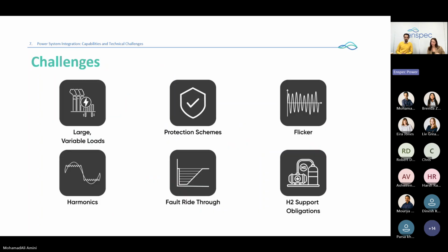In addition to these capabilities, there are some challenges that may arise at the point of connection of a hydrogen electrolyzer plant, mainly because they are large-scale variable loads, as seen in previous slides. These large-scale variable loads could cause issues at the point of connection, depending on their fault ride-through characteristics, and protection schemes at the point of connection might need modification. Also, from a power quality point of view, flicker and harmonics will be the main issues at the point of connection. In addition to these challenges, hydrogen electrolyzers have obligations to support downstream hydrogen users.